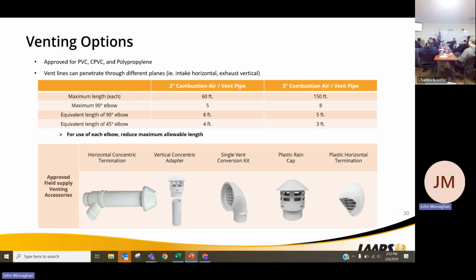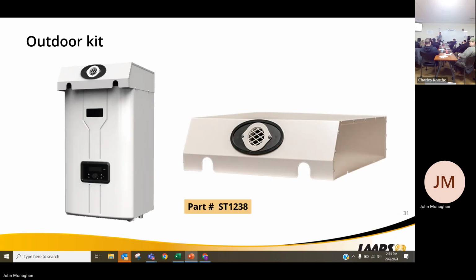Your venting options: concentric terminations, your vertical terminations with your adapter, your plastic rain cap piece on it. Basically it's going to be 60 feet for 2-inch, 150 feet for 3-inch, no more than 5 elbows for 2-inch, no more than 8 elbows for 3-inch. For 2-inch, each 90 counts as 8 feet. For 3-inch, each 90 counts as 5 feet. They're basically going to cut down on your maximum vent lengths.